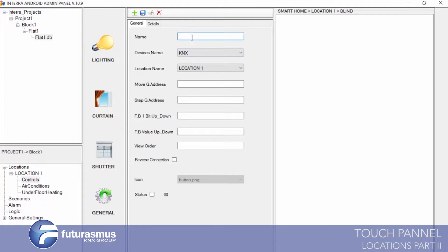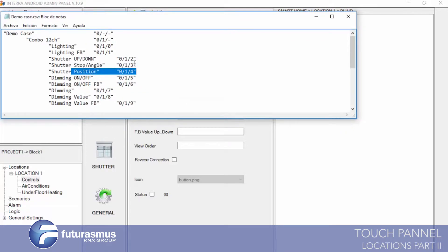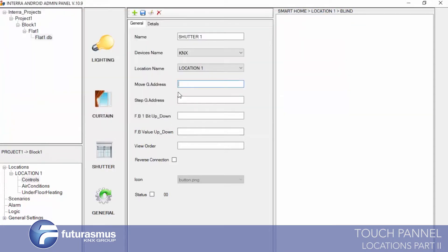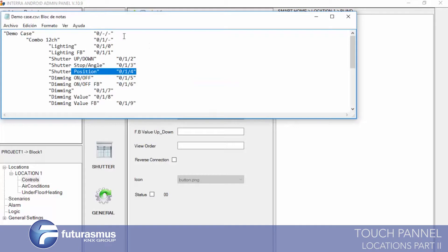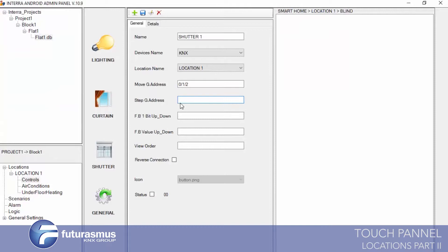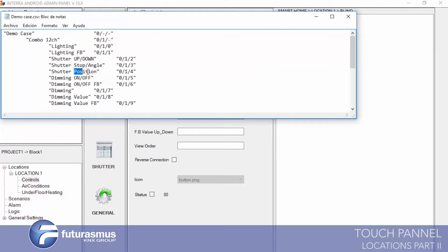So we can define a Shutter. The program asks for move group address again — we are entering the up/down address. We are entering the step, stop, and angle address. And the other one is position: we have a one-byte position value, and we are entering this to the value feedback area.